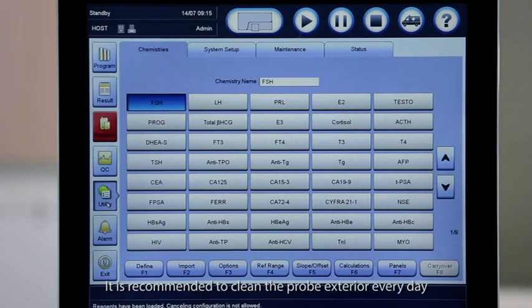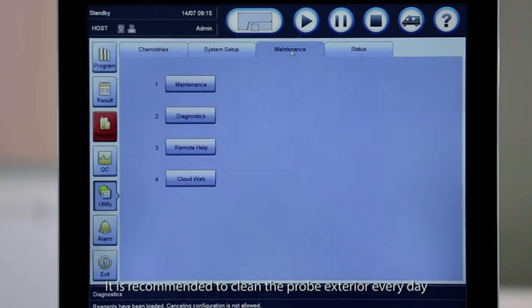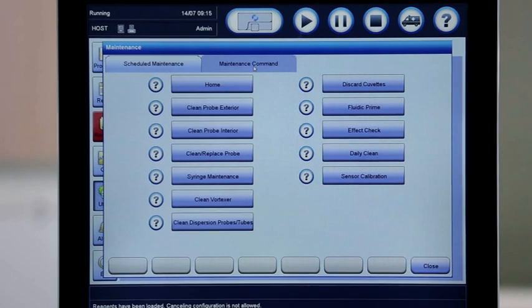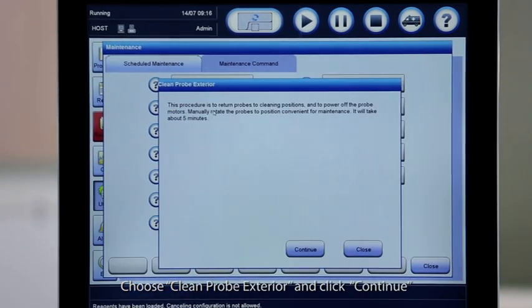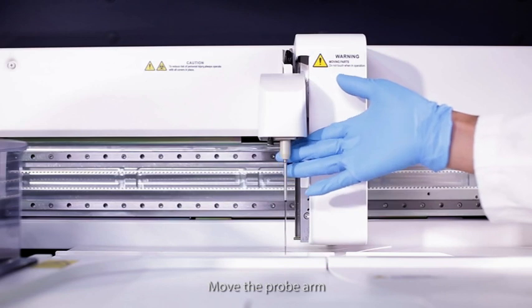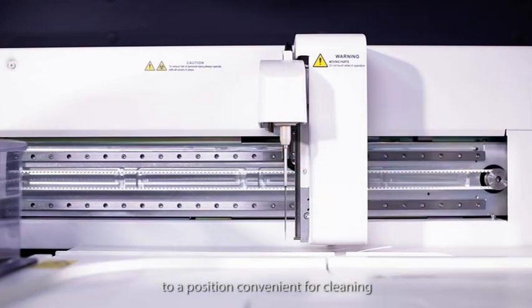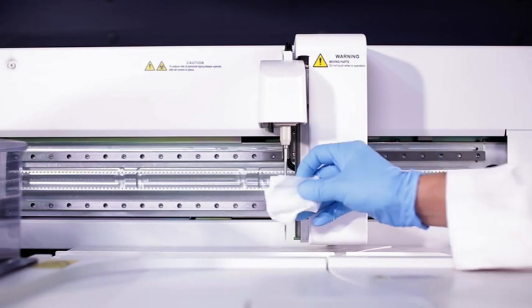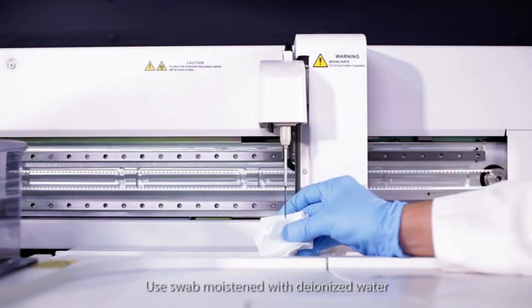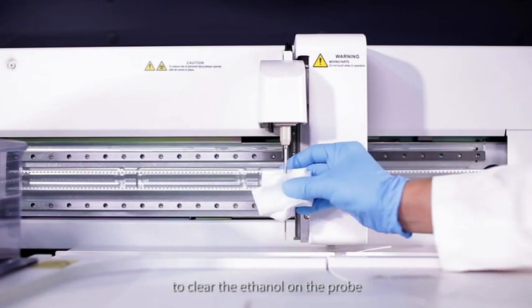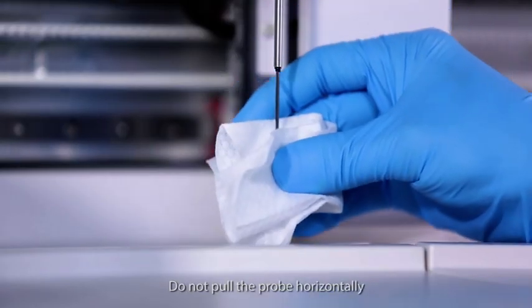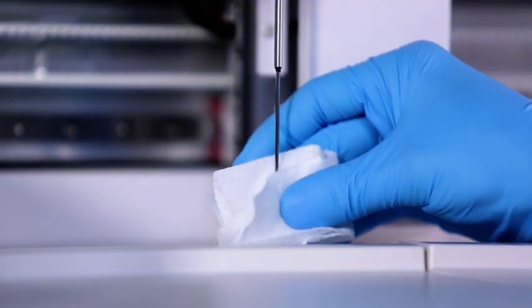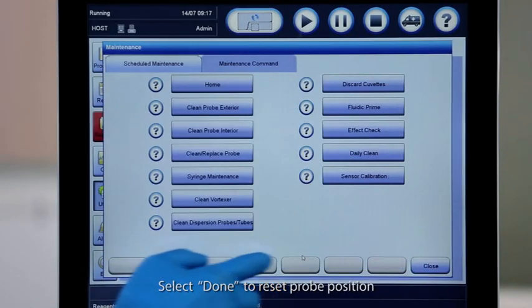It is recommended to clean the probe exterior every day. Go to Maintenance and click Maintenance command. Choose Clean probe exterior and click Continue. Move the probe arm to a position convenient for cleaning. Use alcohol swab to gently wipe the probe. Use swab moistened with deionized water to clear the ethanol on the probe. Do not pull the probe horizontally to prevent probe damage. Select Done to reset probe position.